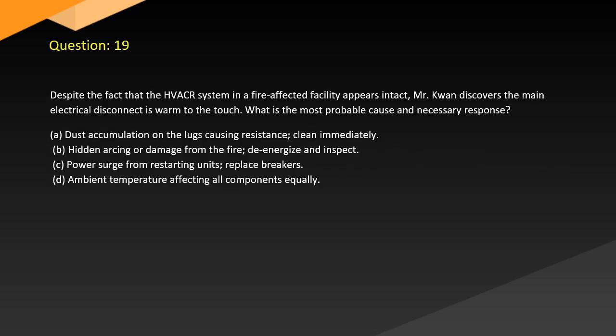Question 19. Despite the fact that the HVACR system in a fire-affected facility appears intact, Mr. Kwan discovers the main electrical disconnect is warm to the touch. What is the most probable cause and necessary response? A. Dust accumulation on the lugs causing resistance. Clean immediately. B. Hidden arcing or damage from the fire. De-energize and inspect. C. Power surge from restarting units. Replace breakers. D. Ambient temperature affecting all components equally.